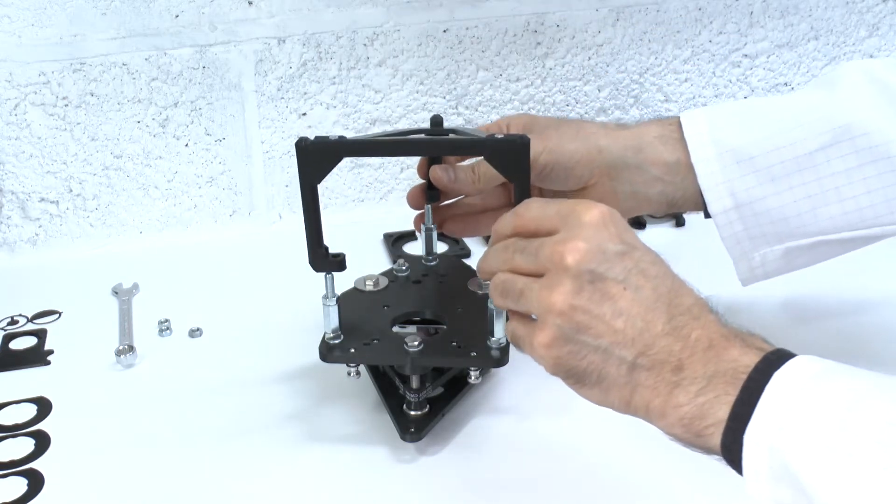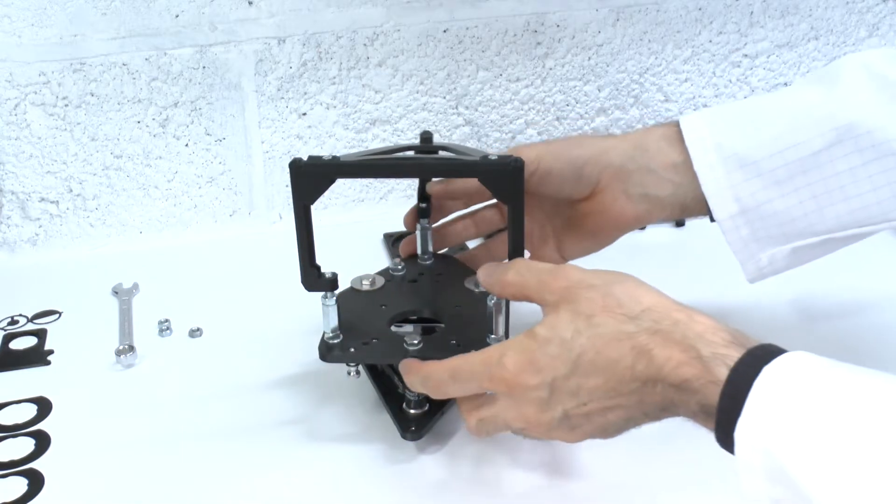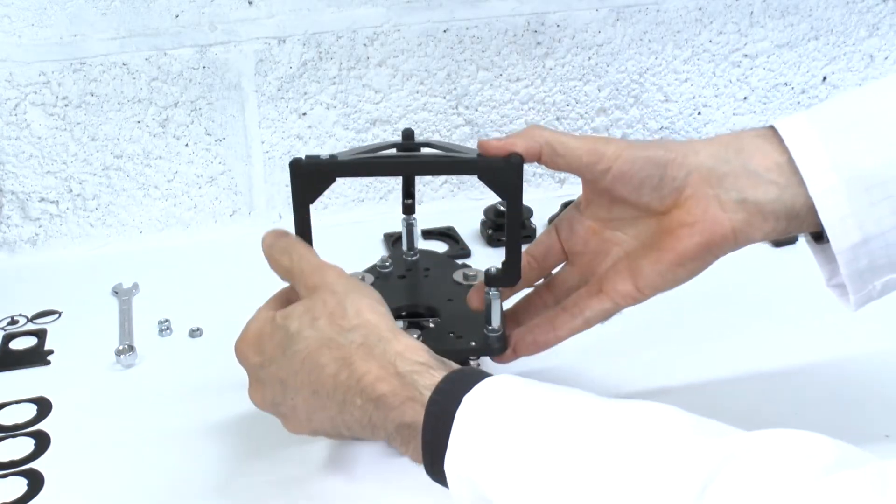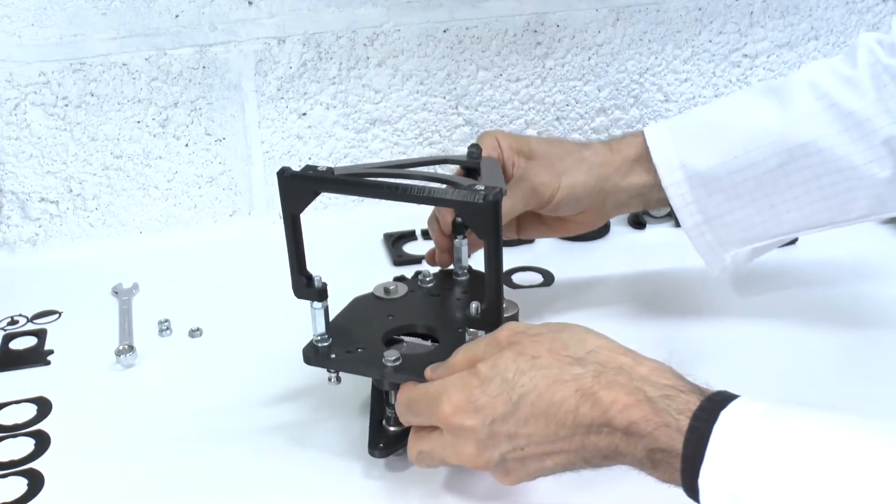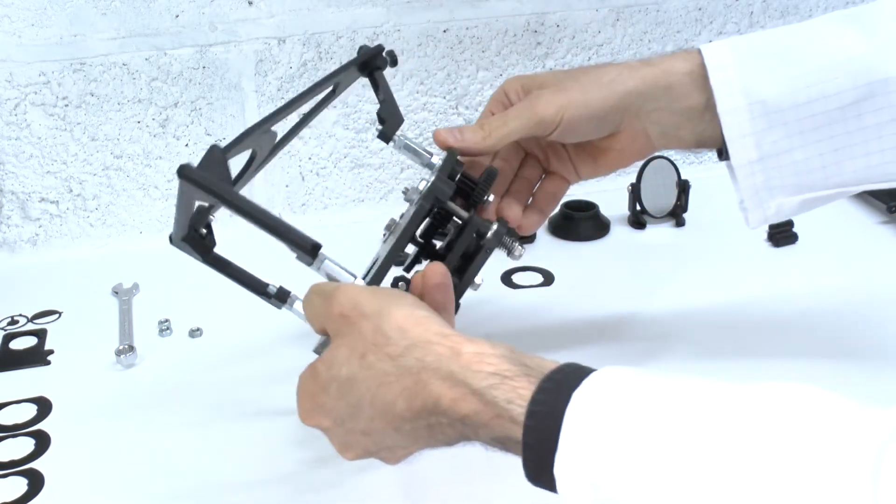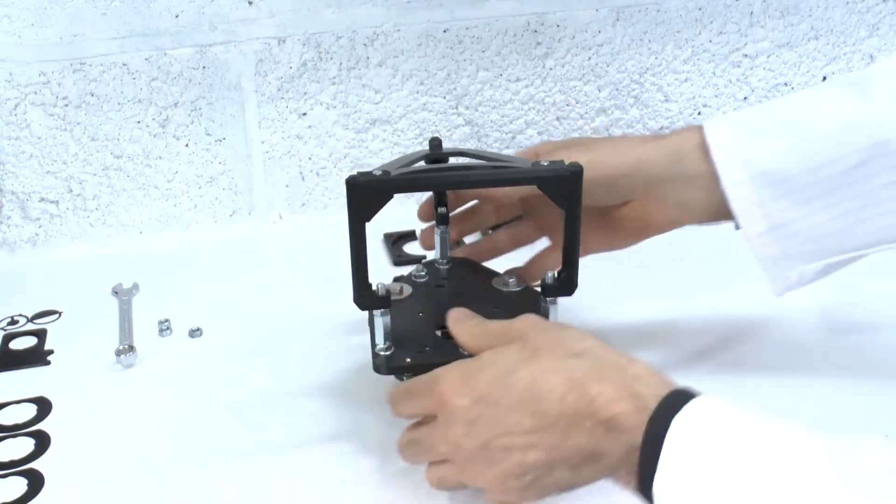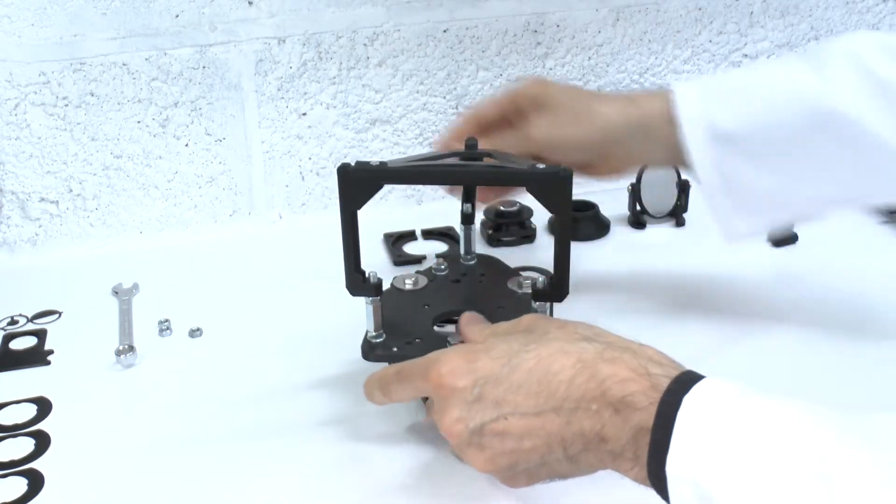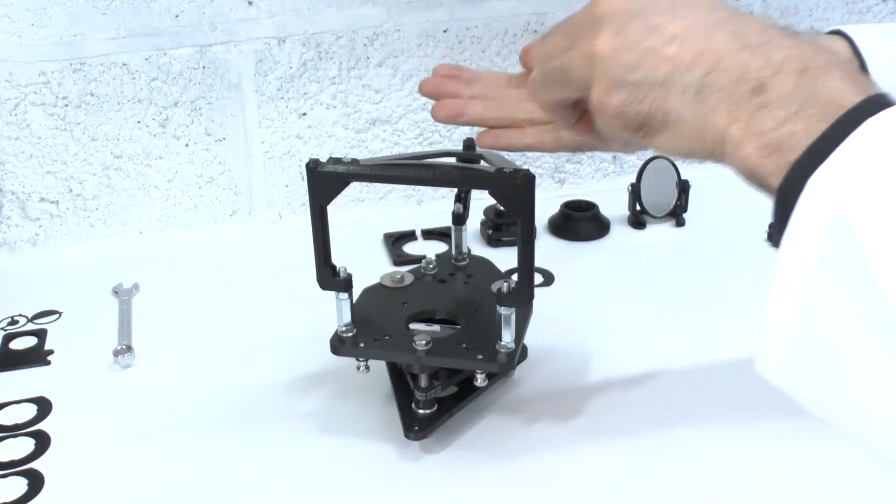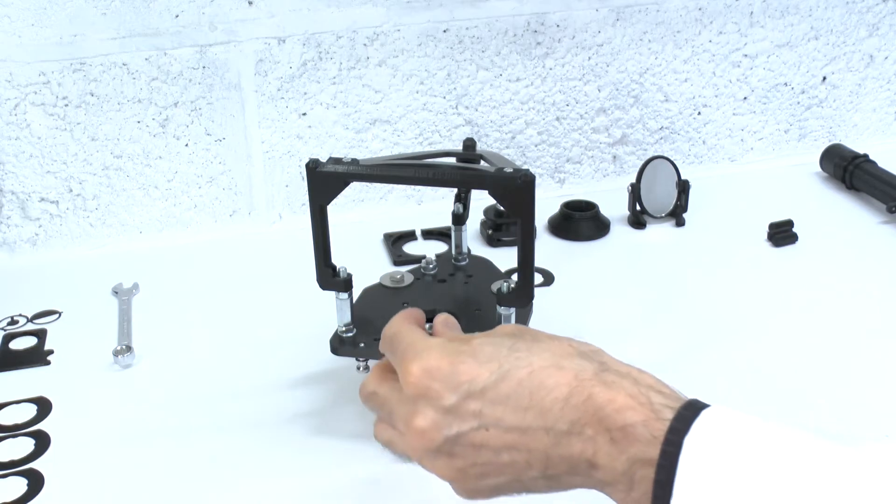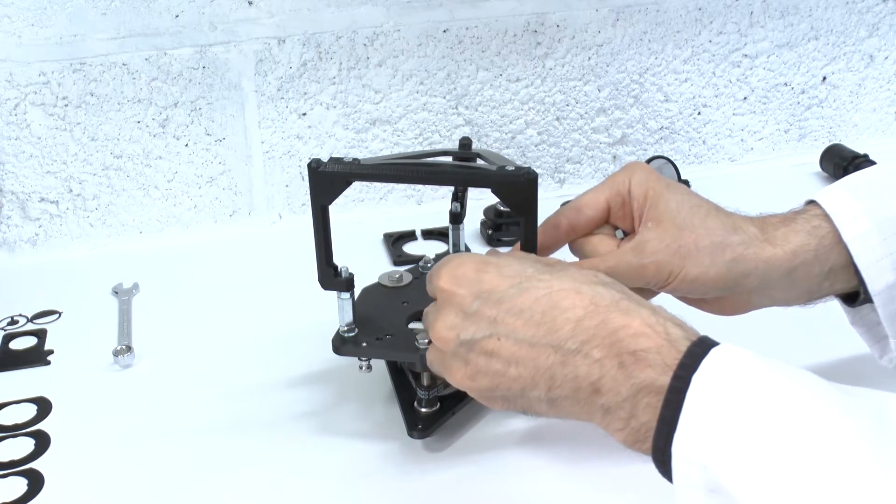With the long leg system assembled, slide the holes over the bolts of the spacers. This may be a bit fiddly or a tight fit, so bear with it and try to move them all a little bit at a time to ensure everything is level as you go down. Once in place, fix everything with three more M6 nuts and tighten them a little to ensure they don't come loose. A 10mm spanner may be used here, but take care not to over tighten.